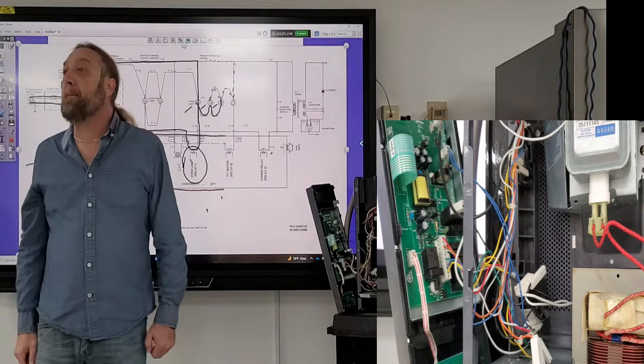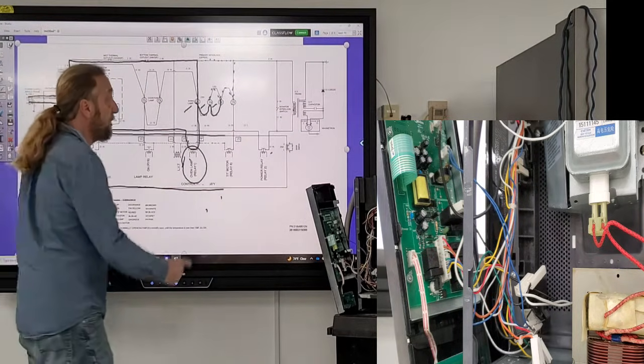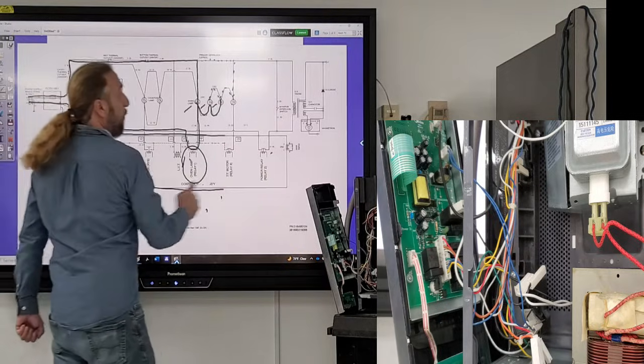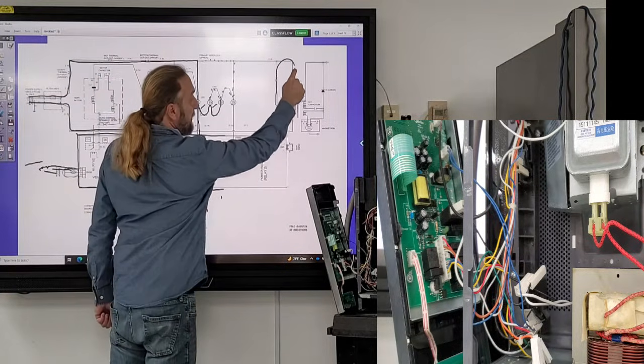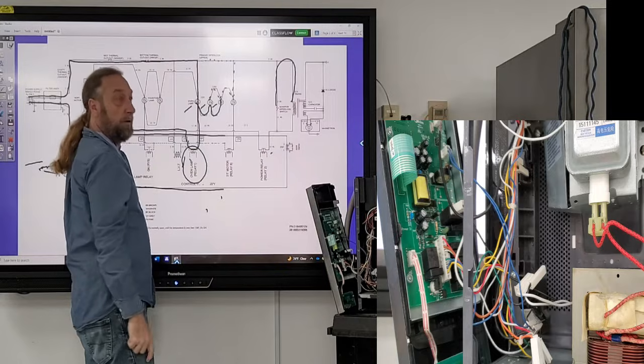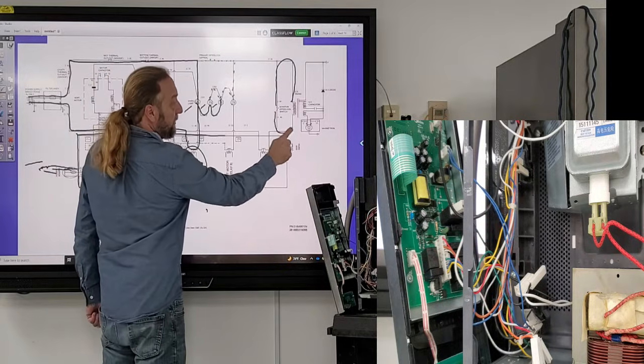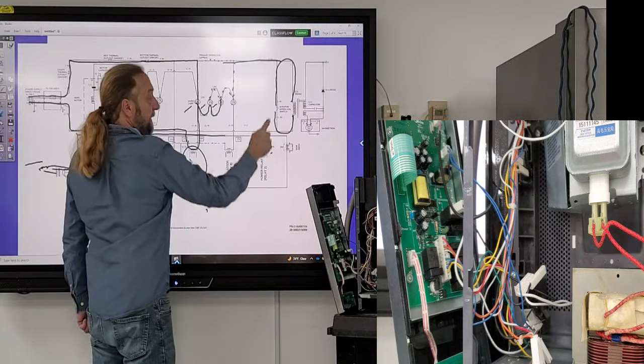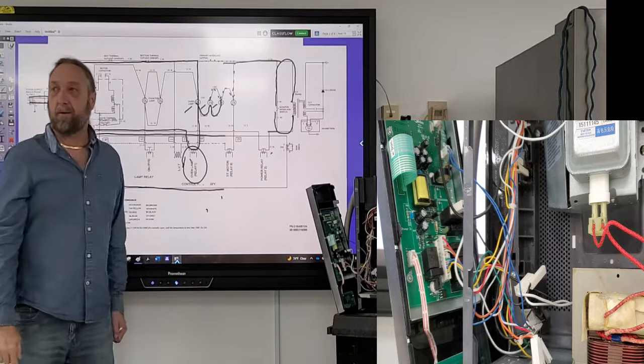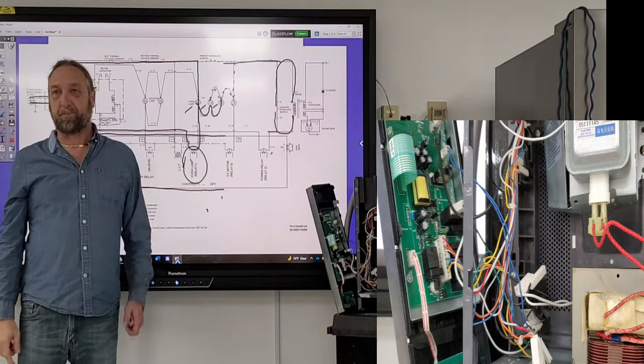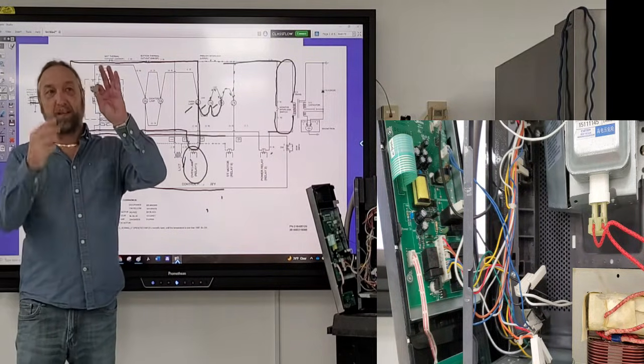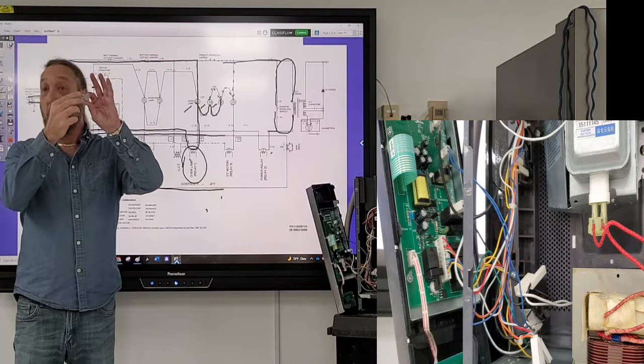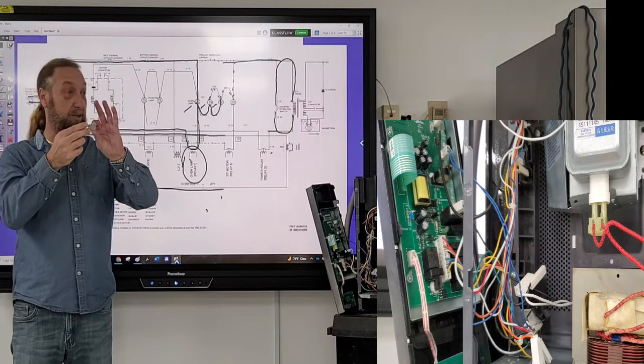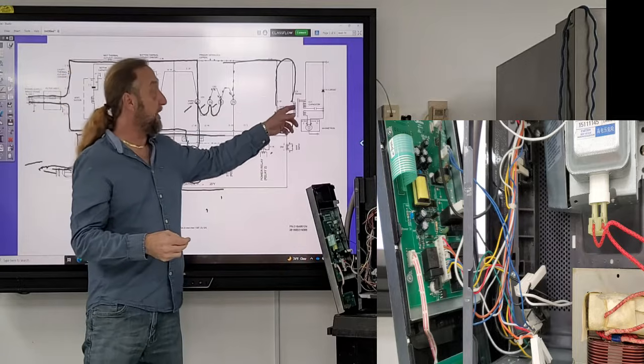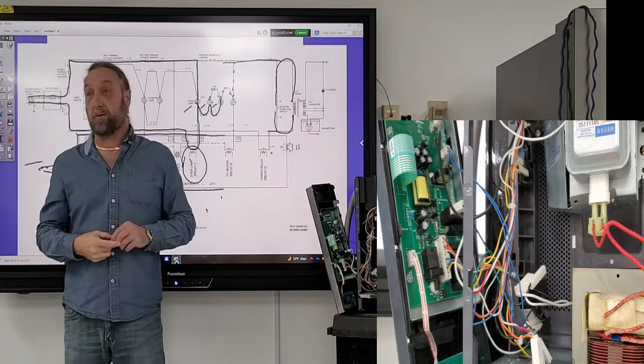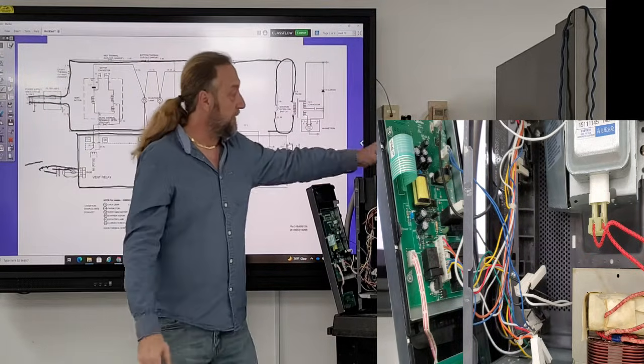Well, check from the monitor switch, because if you look, one side of the monitor switch is one side of the transformer. The other side of the monitor switch is the other side of the transformer. So you should be able to check the power coming to the transformer through the monitor switch. If I check the power going to these two wires on the monitor switch, it's the same as checking power to my transformer. So let's see how we do that.